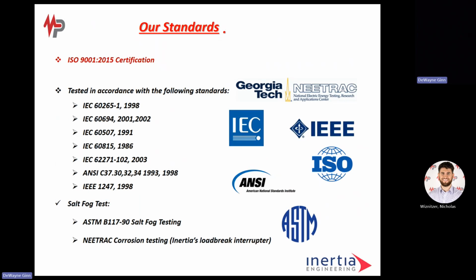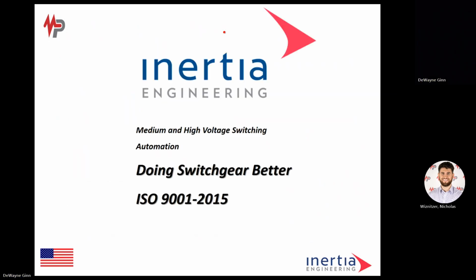Our standards: we build to IEC standards, ANSI C37.30, IEEE 1247. We also salt fog test to ASTM B117. We've salt fog tested at NEETRAC in the Georgia Tech area. We primarily use two different third-party testing facilities, PowerTech in Canada and KEMA in Pennsylvania, for our test reports. But these are our standards all the way around.